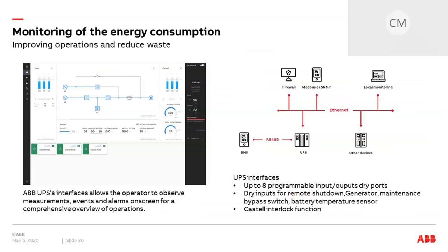Better monitoring allows a data center operator to manage the power consumption and operations. For example, local UPS interfaces allow them to check inputs, outputs, battery voltage and currents, power consumption, temperature measurements for critical components, event alarms, as well as UPS status and primary components status. Those data and analytics can be integrated into the building management systems for remote monitoring. The connectivity is accomplished via SNMP or Modbus TCP/IP.